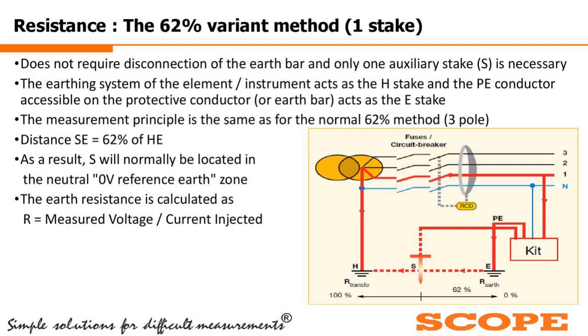Now coming to the single stake measurement, which is also called the single stake measurement with 62% variant method. Why is it called single stake? Because it also does not require any disconnection of the earth bar. Only one auxiliary stake is necessary, as shown in the picture in the center, as you can see.